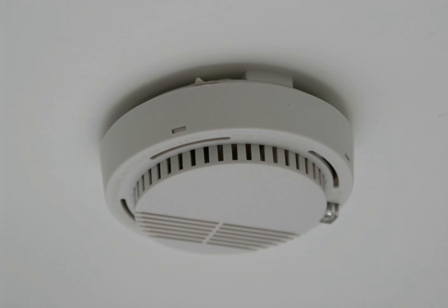Smaller, less expensive smoke alarm systems, typically used in a domestic residential environment, may be individual stand-alone units or interconnected. They typically generate a loud acoustic warning signal as their only action. Several detectors, whether stand-alone or interconnected, are normally used in the rooms of a dwelling. There are inexpensive smoke alarms that may be interconnected so that any detector that triggers sounds all alarms. They are powered by mains electricity with disposable or rechargeable battery backup, and may be interconnected by wires or wirelessly.